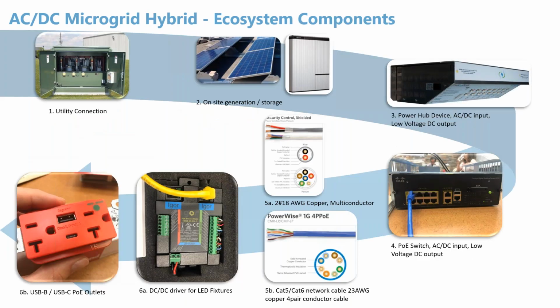The AC/DC microgrid hybrid ecosystem components. In this picture, we're going to show you the different types of components that we discussed previously in the first slide. The utility connection: the connection between the utility and the building is done through medium voltage switches that feed transformers, and they lower the higher voltages, 13.2 kV, or even higher, to a more utilization voltage of 480 volts, 277/480, 120/208. Then we have the on-site generation and the storage. The on-site generation could be PV.